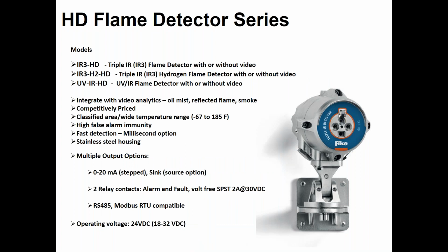Now, the new flame detector series covers IR3, IR3H2 for hydrogen, and UVIR HD. So all three versions have HD video cameras, or you can purchase the detectors without the cameras if they're not used. The detectors with the cameras can be monitored with the video analytics. The reflected flame is very helpful in applications where the fire could potentially be outside of or obstructed and not within the view of the detector itself.